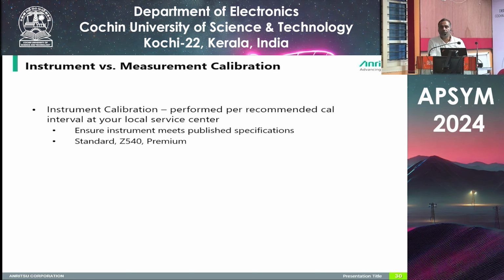And whenever you are connecting to the network analyzer, you will be connecting an adapter or a cable to the front end of the ports. So all these induce some noise and magnitude and phase variations. To nullify or offset that, we will be doing the calibration at the end of the cable. Okay, to nullify or remove those errors, we will be doing the calibration at the end of the cables or the network analyzer ports. Okay, so there are two types of calibrations. One is called instrument calibration, and one is measurement calibration.